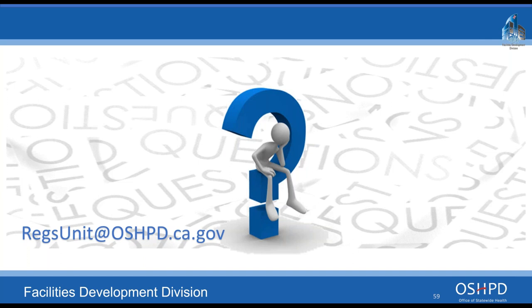Okay, another great question. In order to meet CMS requirements, it's ASHRAE 170 2008. It's the very first version of ASHRAE 170, which none of us really like because there's all kinds of nice advancements beyond that. OSHPD has specifically adopted ASHRAE 170 2013 through Addendum AE. We have that specifically in the code right there in that section of the mechanical code. For all intents and purposes, there really are no conflicts for ventilation requirements between that version and the official 2008 version. So to answer that quickly, it's a very early version of ASHRAE 170. So hopefully that answers that.